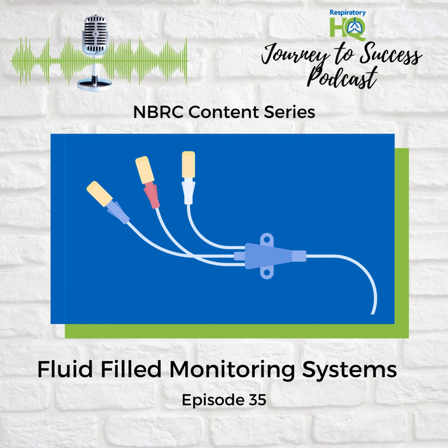So how does it actually work? I mean, how do they measure these pressures? Well, there are a few ways to do it. The most common method uses a fluid-filled system connected to a transducer. When I see those wavy lines on a hospital monitor, the ones that go up and down with a heartbeat, I always wonder, what are those really showing? Yeah, good point. Those lines are a visual representation of the pressure changes happening inside the heart or blood vessels. It all starts with a thin tube called a catheter. It's inserted into a blood vessel or heart chamber and acts as a sensor. It picks up pressure changes and transmits them through extension tubing to the transducer.